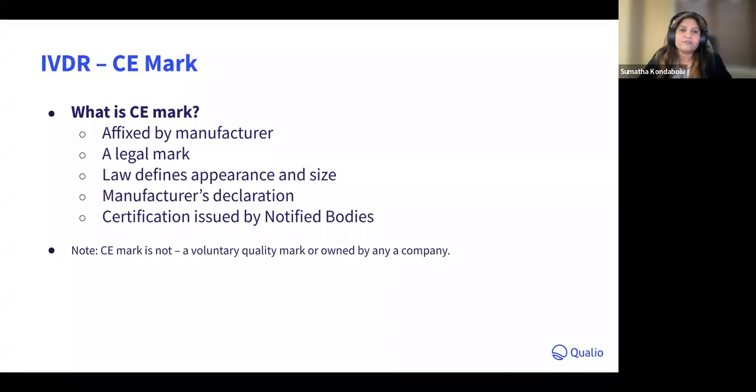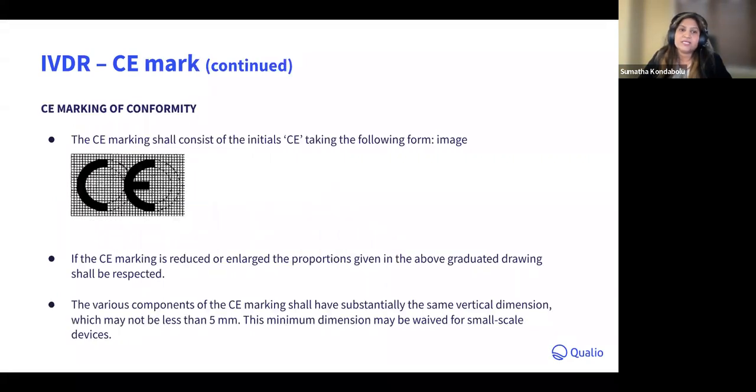Specifically, it is required for a certification that is issued by the notified bodies. So that's where it's important that you comply with this requirement. If you see in the next following slide, this is how it should actually look. There could be some different variations in the CE mark, so please make sure that you are following the right dimensions and the requirements specified by the guidance documents.